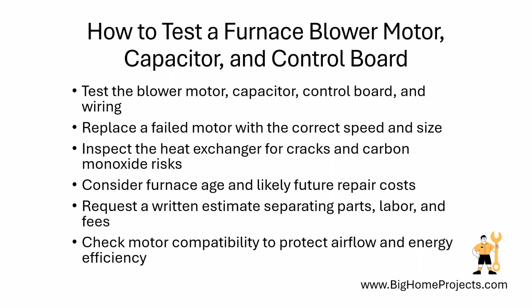The blower motor moves warm air through your home, so a failed motor does not automatically mean the whole furnace has failed. A technician should test the motor, capacitor, control board, wiring, and air filter before recommending replacement. Sometimes a weak capacitor makes the motor seem broken, and replacing that small part may solve the problem. If the motor is noisy, overheating, or drawing the wrong amount of electrical current, replacement may be sensible.